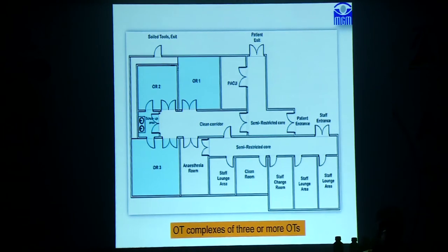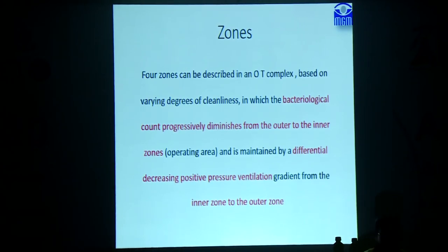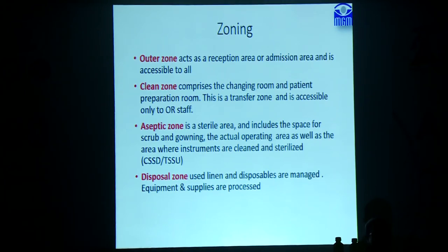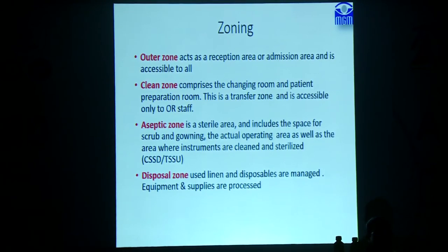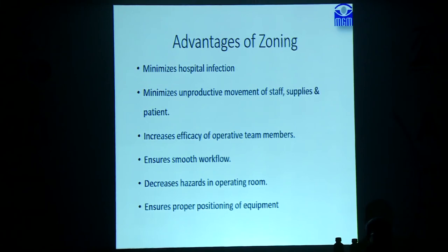There are four zones in the OT based on infection control, varying on the degree of cleanliness in which bacteria progressively diminish from the outer to the inner zones. This is maintained by a differential decreasing positive pressure ventilation gradient from the inner zone to the outer zone. The outer zone acts as a reception and admission area accessible to all. The clean zone comprises the changing room and patient preparation room, accessible only to staff. The aseptic zone is sterile and includes scrub, gowning, the actual operating area, and instrument sterilization. The disposal zone manages linen and disposables.